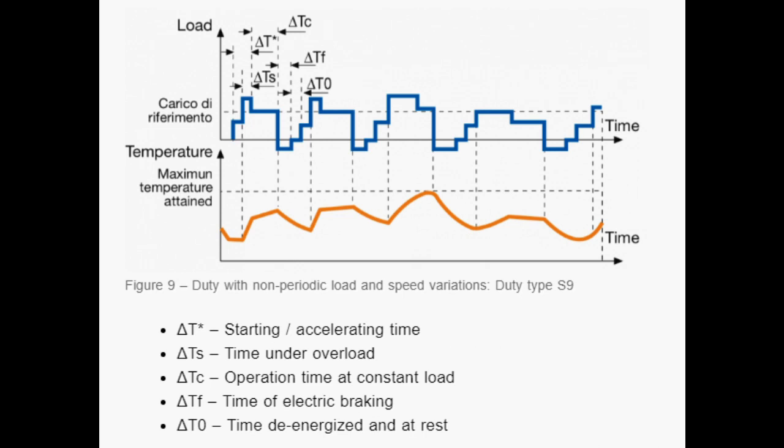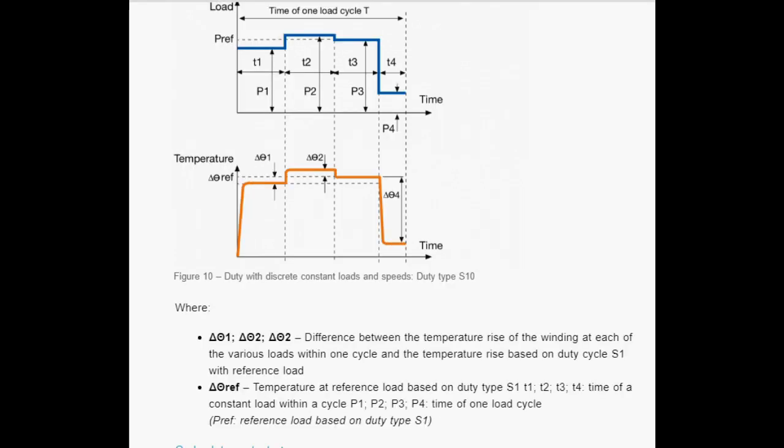S9 is defined as a duty in which generally load and speed vary non-periodically within the permissible operating range. S10 is defined as operation characterized by a specific number of discrete values of load and maintained for sufficient time to allow the machine to reach thermal equilibrium.